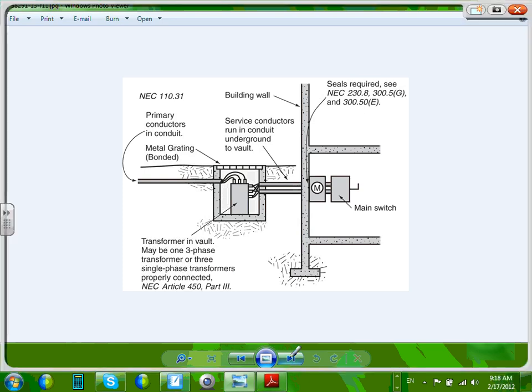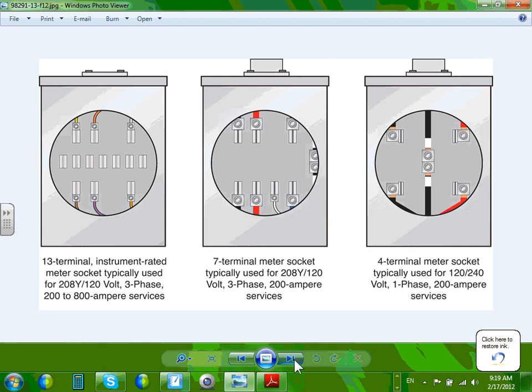So service conductors run into the building. Sometimes they put the service point right here. If the service point is right here, who owns everything from here on? The utility. You have to decide where the service point is. Every utility has it slightly different. I'll show you in a second here. Really nice pictures about service point.